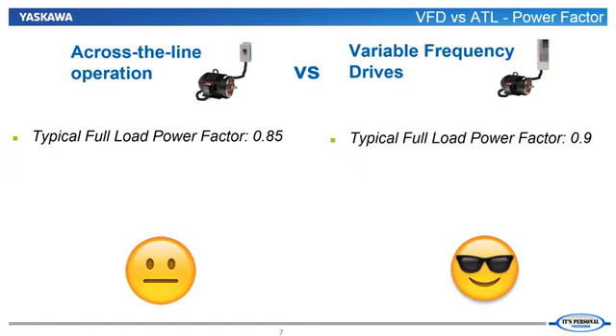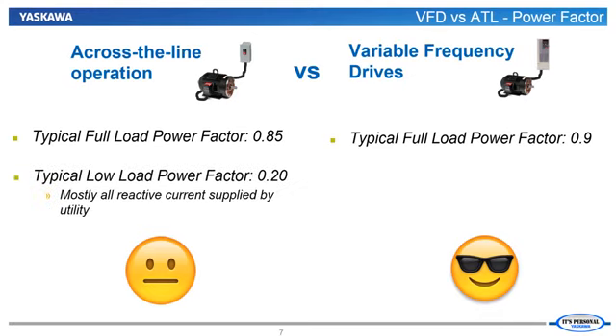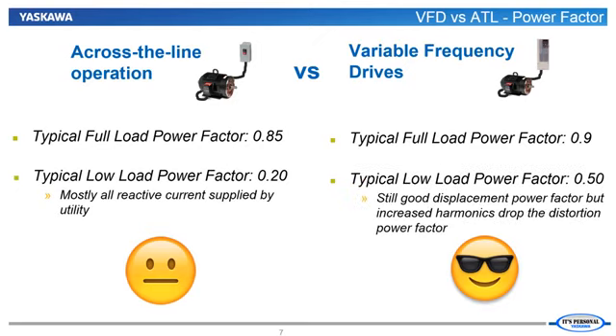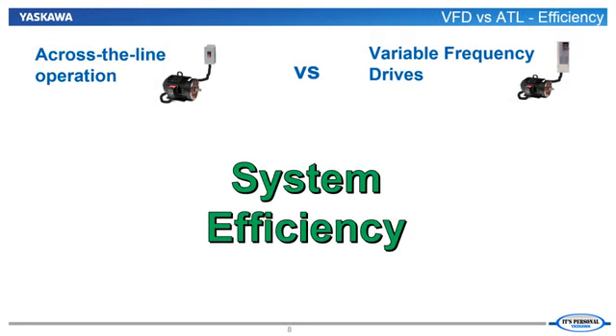The VFD will have its own effect on the power factor, but the trade-off is clearly in favor of using the VFD. During low loads, proportionally more current is being used for magnetic fields than for driving the load, so the power factor drops pretty drastically. However, with the VFD, the magnetic fields can be fed from the drive's DC bus, so from the point of view of the utility, there isn't quite such a drop in power factor. Our next comparison will be in system efficiency, which we already kind of tipped our hand about when we discussed the VFD's ability to automatically regulate speed to meet actual demand.